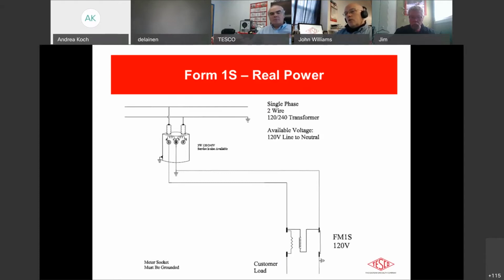So the simplest form that we have here is the 1S meter form. It's typically a single phase 120 volt application where you have one side of a standard 3-wire pole transformer going into the meter. You have the voltage coil across and the current coil down. The meter is in line with the power source and the load, and is measuring the energy directly into the customer load. Right. This is a self-contained application where there are no other external devices needed for the meter to meter properly.